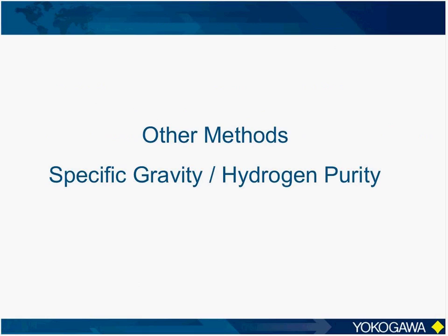Now, these are just a portion of the applications that can benefit from vibrating element systems. Other applications include measuring the density of fuel gas to correct orifice-type flow meters. Also, specific gravity can be used in compressor control schemes to prevent slugs of light gases from damaging expensive equipment. So now what we want to do is briefly discuss other methods available to make these measurements so that you're able to compare and contrast them with the vibrating element technology.